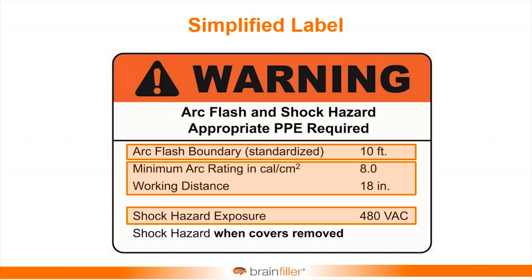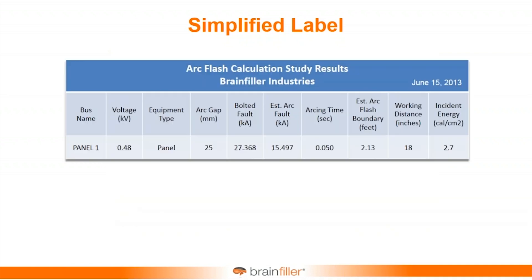It makes it so much simpler. You want to add the working distance — I can't emphasize that enough. That's not required in 70E, but in my view you need to know what distance that arc rating is associated with. And then of course the shock hazard. What makes this simpler is when you perform an arc flash study, you'll have a certain incident energy based at a certain working distance and an arc flash boundary. Someday you may go back and rerun the analysis, and when that happens, numbers can change — short circuit currents may go up or down, clearing times may go up or down, and the incident energy and arc flash boundary may go up or down.